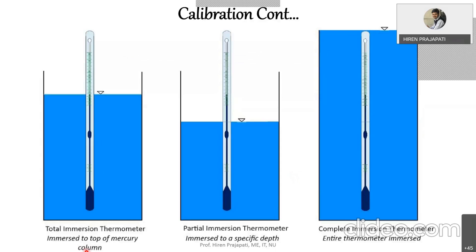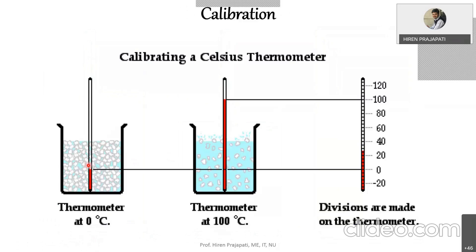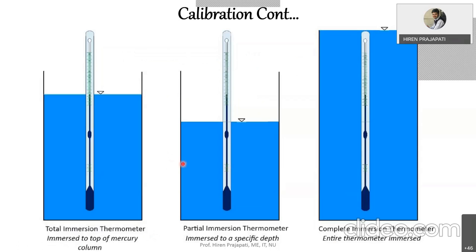The three types of thermometers based on calibration conditions are: total immersion, partial immersion, and complete immersion. For total immersion, you immerse the thermometer up to the top of the mercury column — meaning the mercury column is entirely within the medium whose temperature you want to measure.